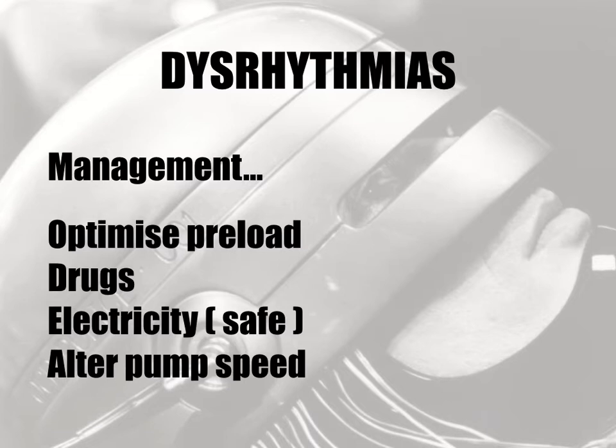Once your patient arrives at their VAD coordinating centre, their cardiologist may choose to alter the VAD pump speed. This typically takes place under transesophageal echo guidance, taking into consideration the important data downloaded from the VAD.